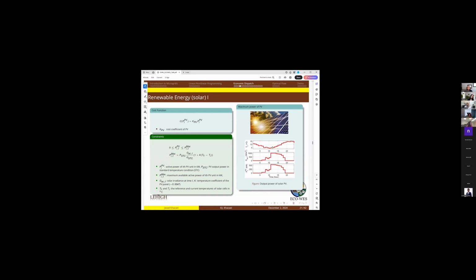For example, given a current temperature profile and solar radiation profile over 24 hours, putting these into the equation gives the output power of the solar panel—this is the maximum available power you can get from the solar. You have to bound the power you use between 0 and this maximum. In the past we'd extract the maximum power, but now we have control over the solar panels so we don't necessarily need to extract the maximum. Sometimes we use only a portion of this power for economic dispatch to run the loads, and the rest is used to charge batteries or electric vehicles in the system.